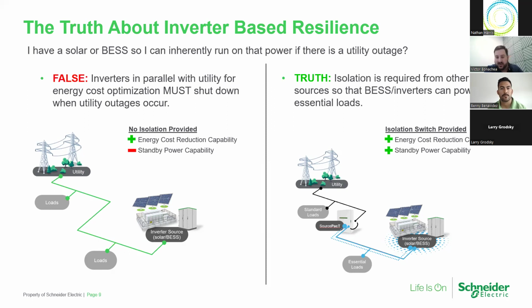That disconnect would be something directly at the output of the inverter so that you can basically take it offline from your entire system and do work on it and ensure that it's disconnected. You can't have that be the same as one of these isolation points, because if you take it off at that point, there's no way for power to get from there to those essential loads. So the isolation for serviceability and for disconnect reasons at the inverter is separate from the isolation or interconnect point to the utility, where you might island part of your overall facility's electrical infrastructure, which includes your inverter as well as your essential load. Those are two separate things that are very easy to mix together sometimes, but they're in fact two different use cases. So let's just keep that in mind.